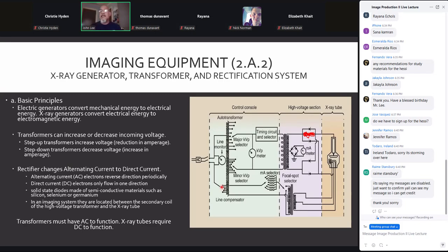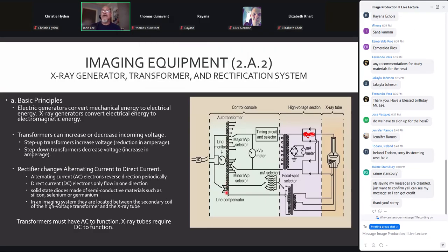Now the line compensation is automatic. All of our stuff is digital, and a lot of these things are controlled by computers or other types of circuitry, so we don't have to manipulate this anymore. That's why we don't see line meters very often. But those lines connect to the auto transformer, single coil. It does have a primary and secondary side. So the primary side would be all of these coils that we tap from here to here. The secondary side is going to include all of these here, but we're only going to use a certain amount.